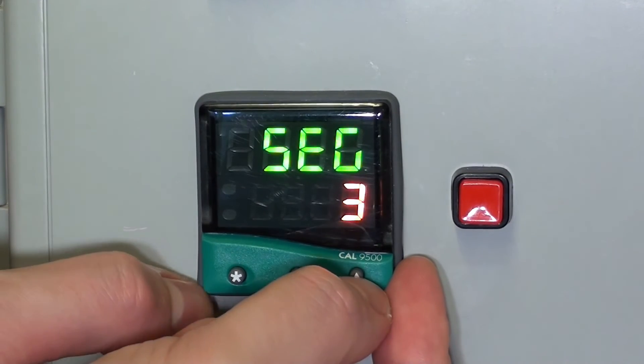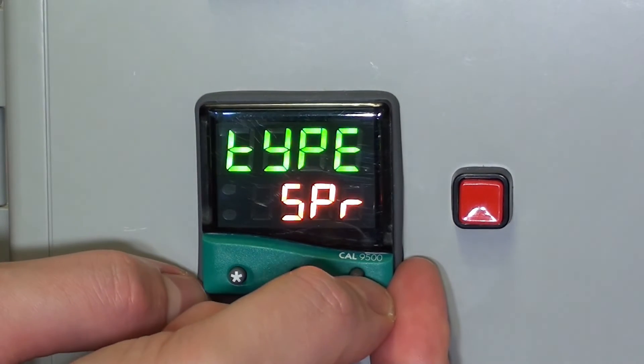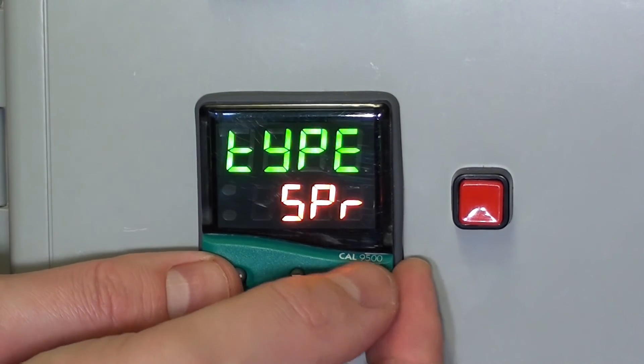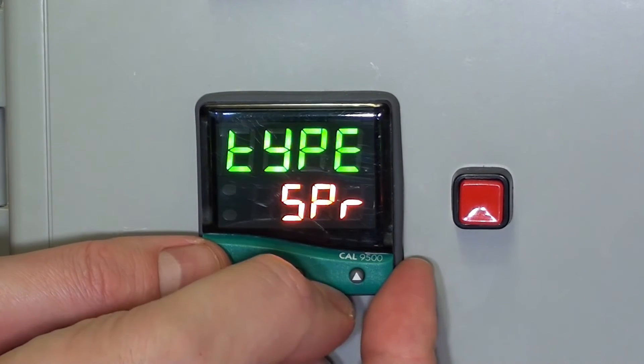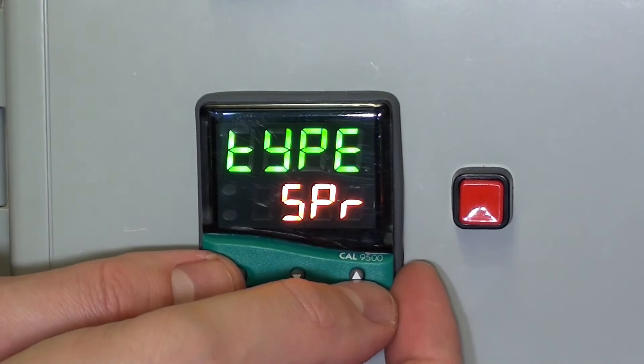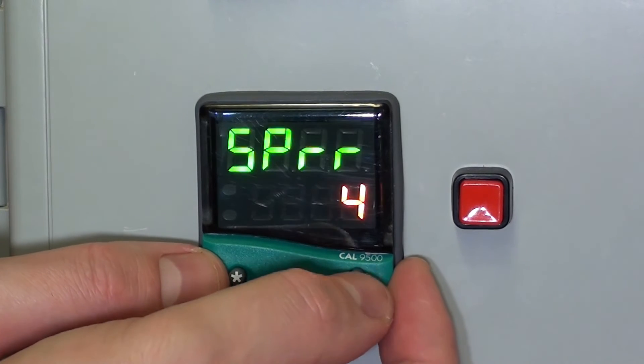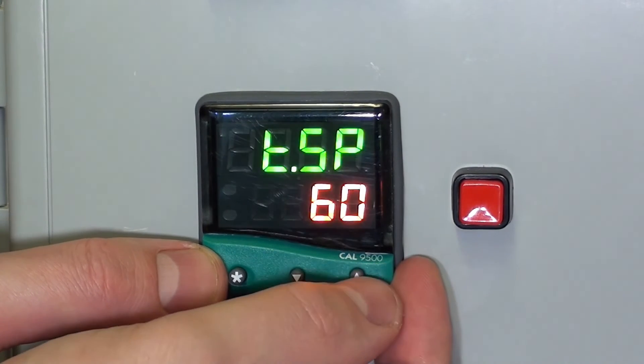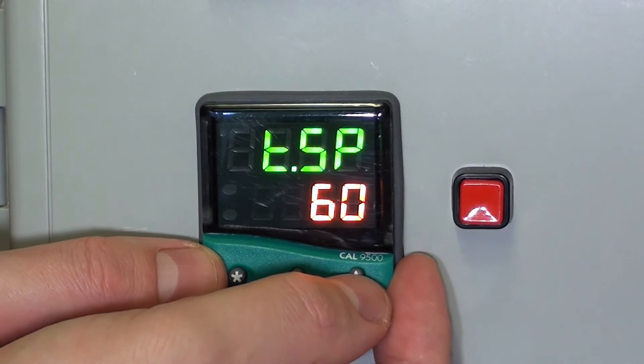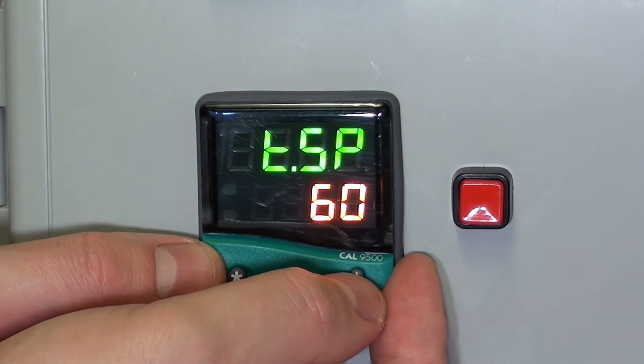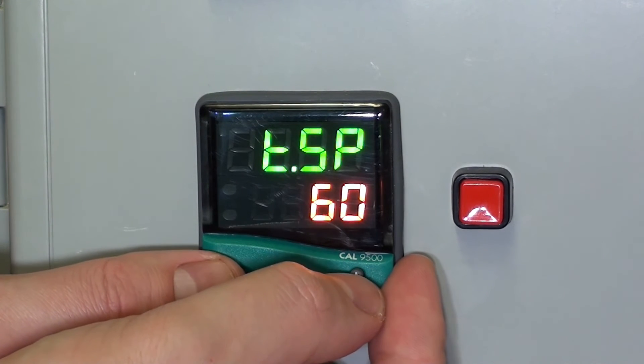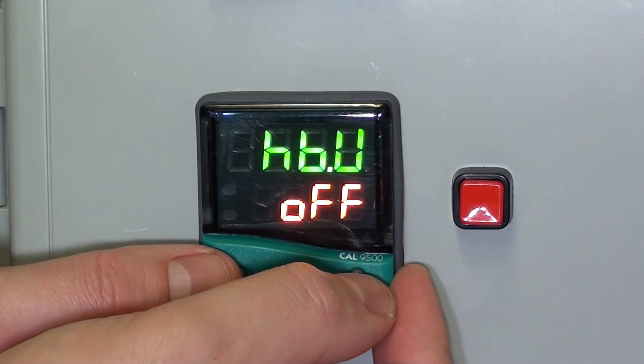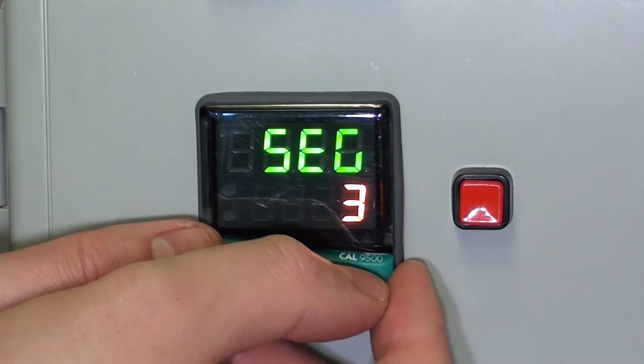Segment 3. Type we want it to ramp up again to 60 degrees, so set point ramp for segment 3. And the ramp rate this time is 4. And the target set point for it to ramp up to is 60 degrees C. That's segment 3.